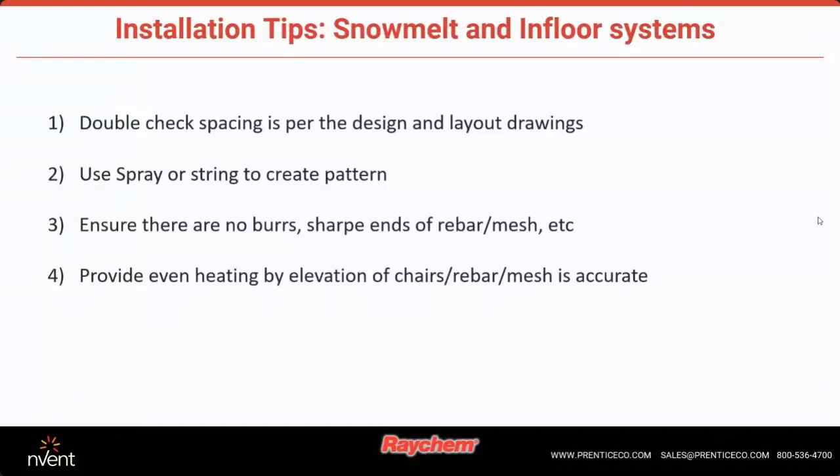If you have a section that the cable is all the way down 4 or 5 inches down to the ground, or you have another area that's 1 inch or less onto the top of the surface, you can get a lot of variations in your melting. You can also cause concrete to prematurely buckle or even bust.